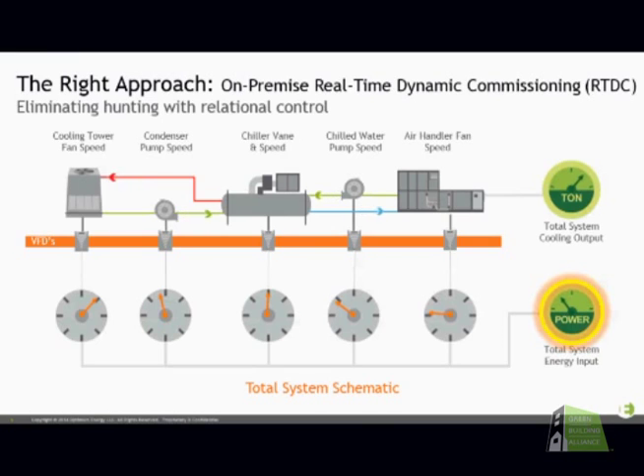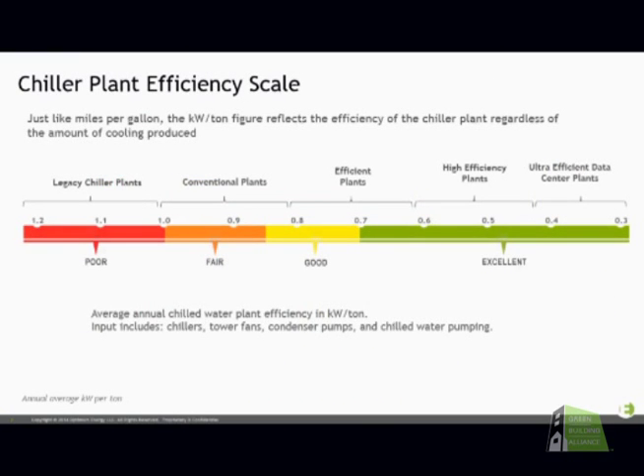So similarly, what we look at is kilowatts per ton. So energy in is kilowatts, or horsepower, which is just a conversion, to tons of cooling. And again, if I'm getting too into the weeds, and you talk somewhat intuitively for what a ton of cooling is, that's 12,000 BTUs per hour, which if you look at one of those small window air conditioning units, that's usually 6,000 BTUs. So a lot of the plants that we're dealing with are many thousand tons, so many thousand of those window air conditioning equivalents.